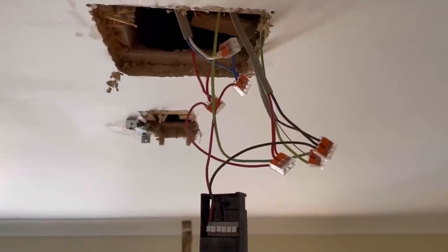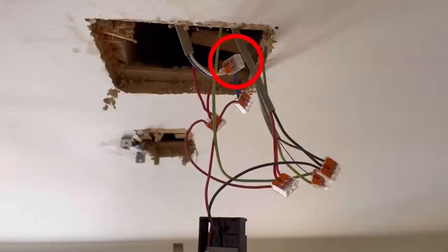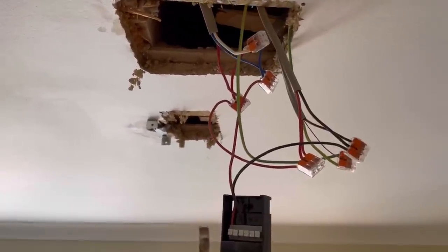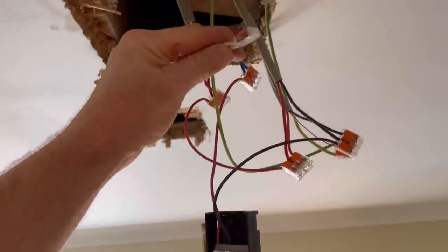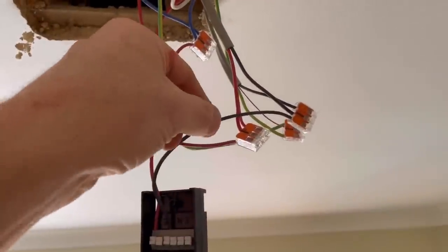It's quite common on a two-way lighting circuit - the commons simply just need to be joined together, whether it's a two-way or two-way and intermediate. The common going from that switch and that switch - in this case we've used the white wire that's just joined together and left as it is on this cable here and this cable here.